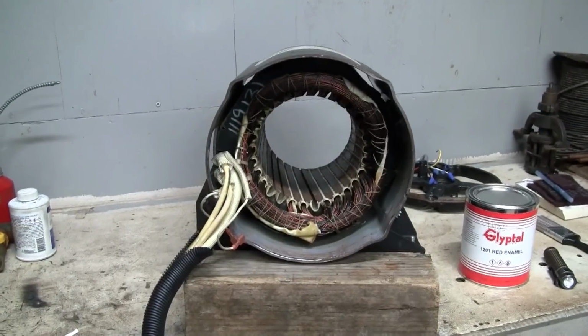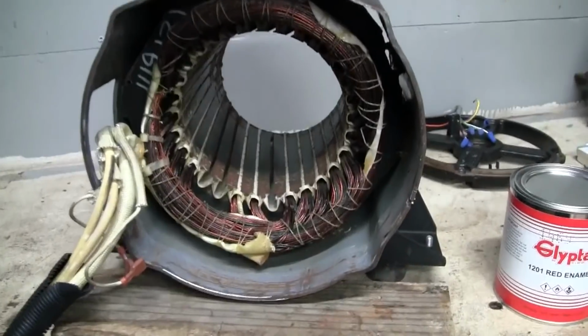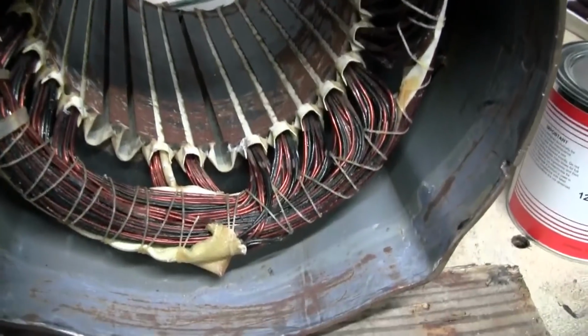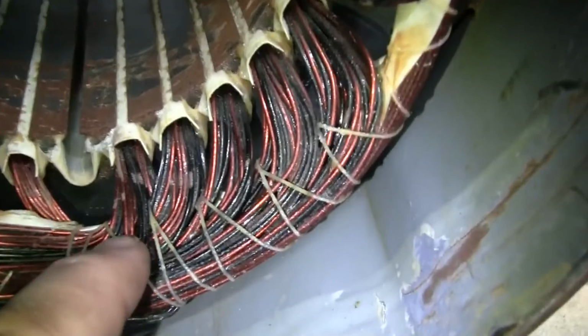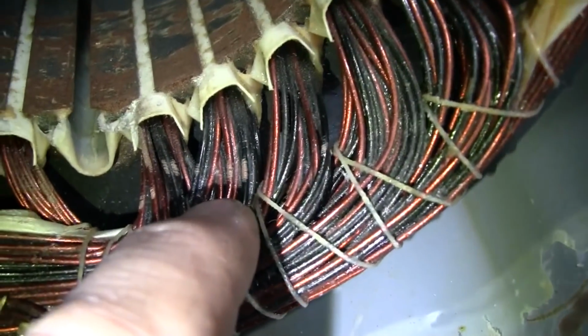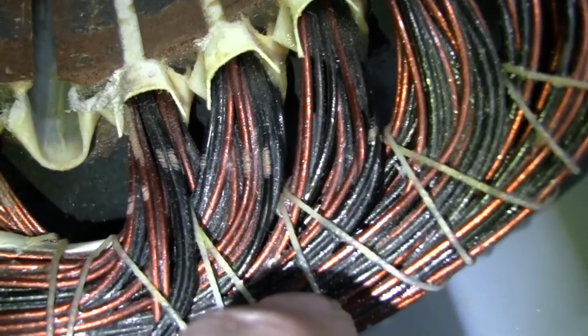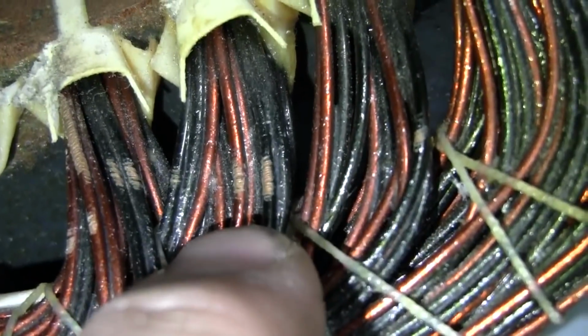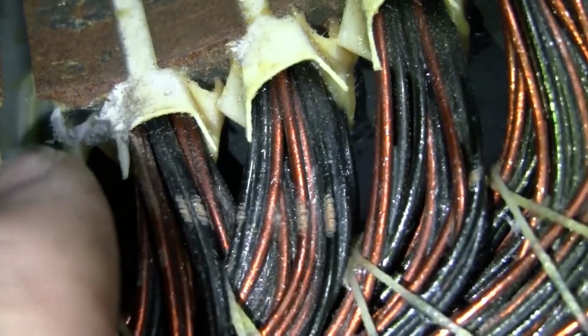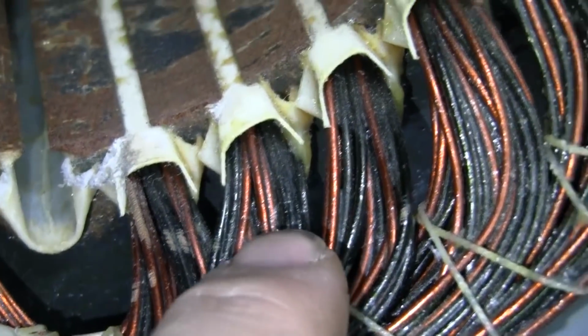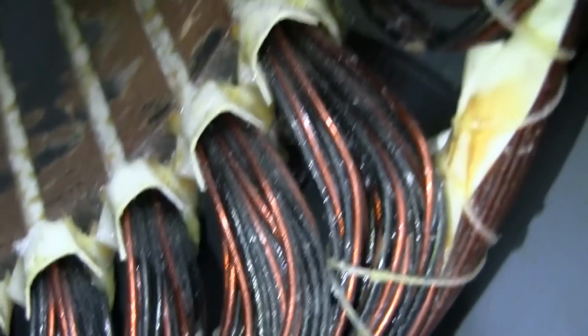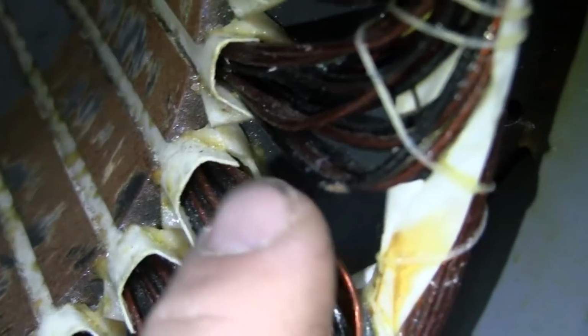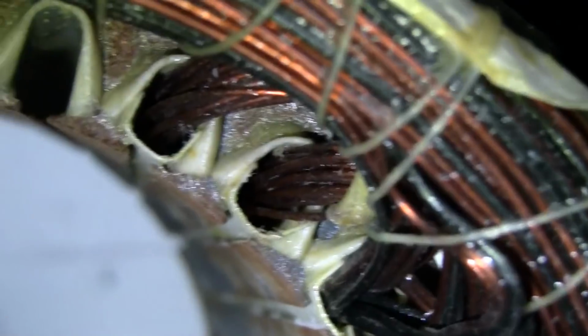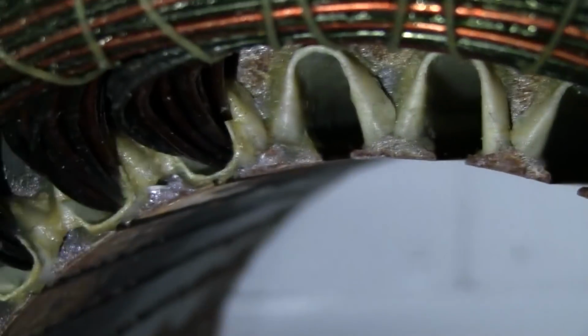While that epoxy is curing on the rotor, let's turn our attention to the stator winding. Remember in the last video, we found these abraded sections of the winding. Let me zoom in on that, where it looks like something either nibbled away or got wrapped around the rotor shaft and was dragging along here and removed the enamel from these pieces of these wire coils. There, and there's a few others around the outside of the stator.